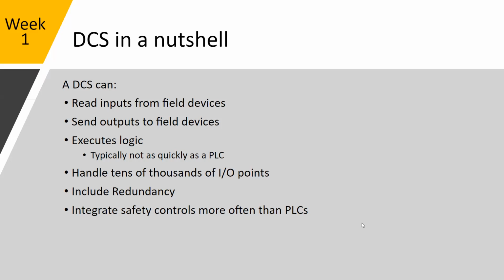The DCSs typically will have some more redundancy features built into them, meaning some of them will have multiple IO cards where you'll wire back multiple inputs for the same device, and the cards will monitor that the wires are still connected. They'll even have multiple PLCs able to communicate back and forth and update and transmit the programs between each other in the event of a failure. And again, integrated safety controls, that's getting into safety as interlocking systems to shut down in the event of failures, more than just light curtains.